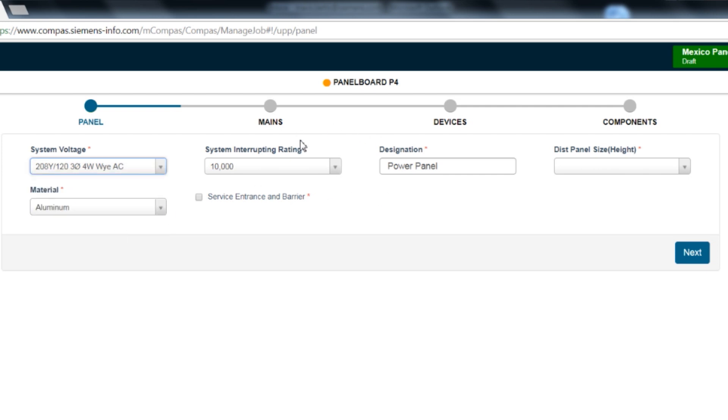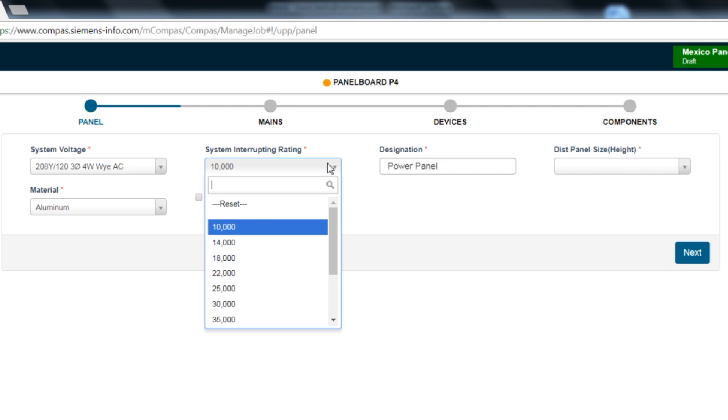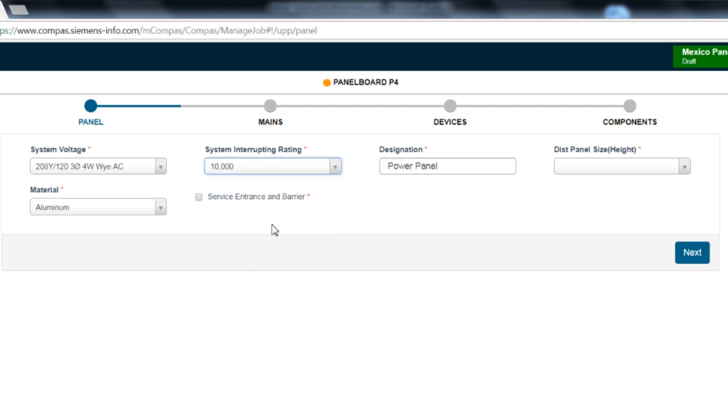The second selection is the system interrupt rating. This will determine the breaker selection. All UPP interiors are rated 200,000 amperes and the system rating is limited to the lowest rated breaker in the panel. For this exercise, we will select 10,000 amps for the interrupt rating.